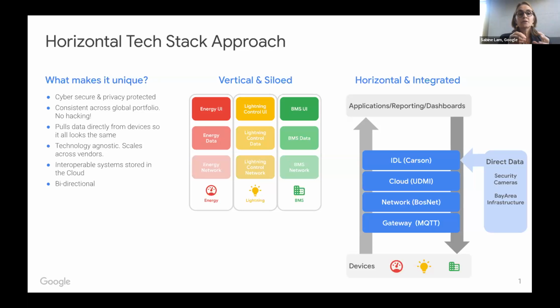As soon as the data leaves the device, it has to be done in a very secure way. So we're looking at different protocols. We're all familiar with BACnet, Modbus, et cetera. By the time the data leaves the device, in our case, we're translating it into MQTT, a more IT-related protocol that is secure, lightweight, and allows a lot of data to go through very quickly in a very secure way. So we also make sure that it's on the Google network. So it's a corp managed solution.